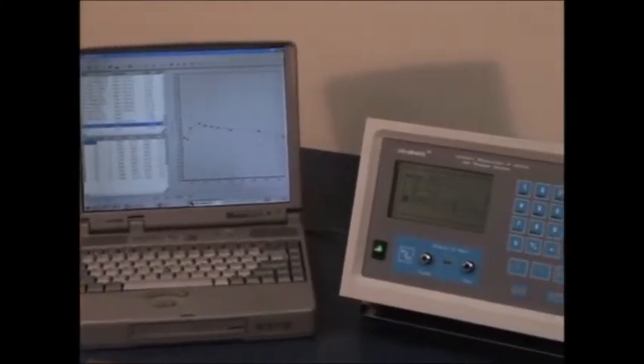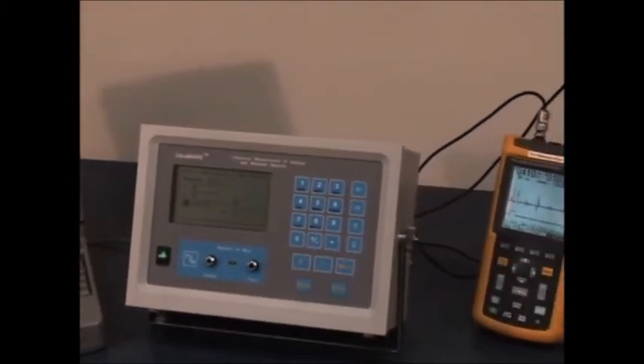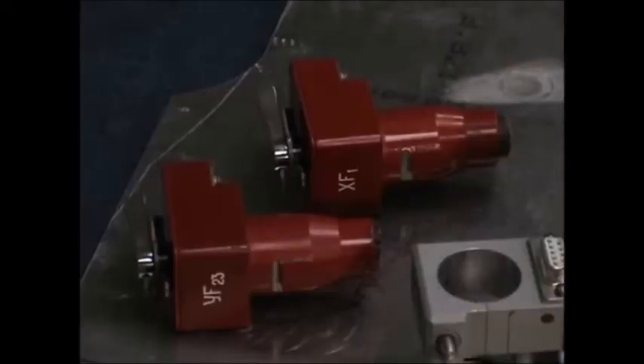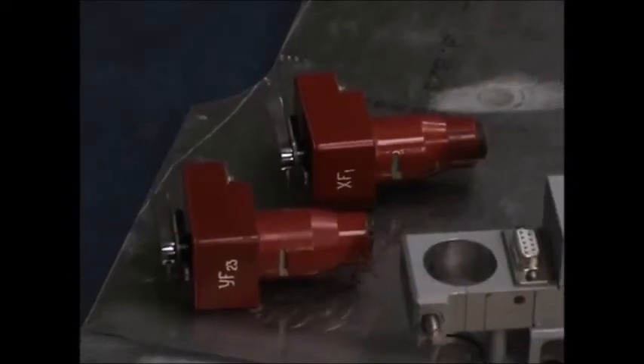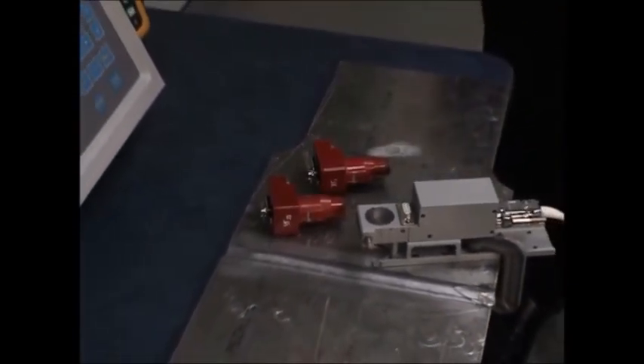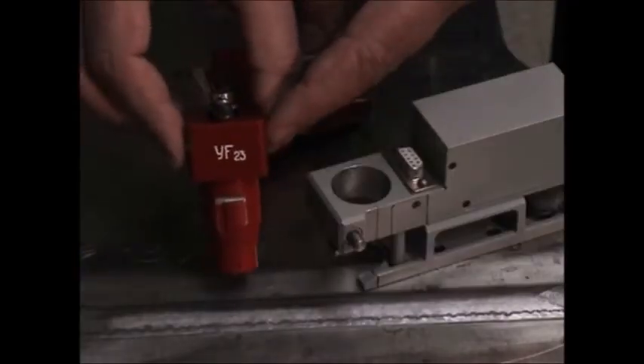Ultrasonic peening treatment efficiency can be evaluated based on ultrasonic measurements of residual stresses in welded elements before and after treatment. The measurement process involves measuring the velocity of two shear polarized waves and one longitudinal ultrasonic wave at the specific point of interest. Two different gauges are used for this purpose.